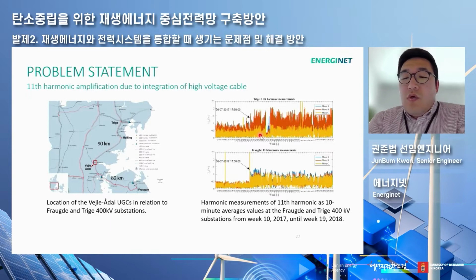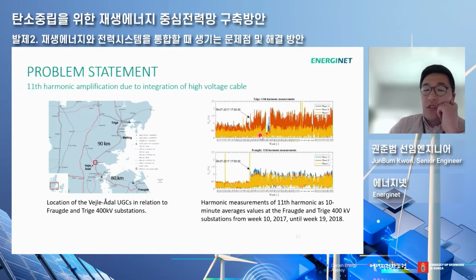But by expanding renewable energy, of course, we need to expand and strengthen the power lines, but residents are against having more lines, so we are using cables. But the oscillation point at HVDCs, when they meet with high frequency issues, will create amplification of high frequency. And when this goes above the 1.5% limit, we might have to install more filters or other ways to reduce this problem.